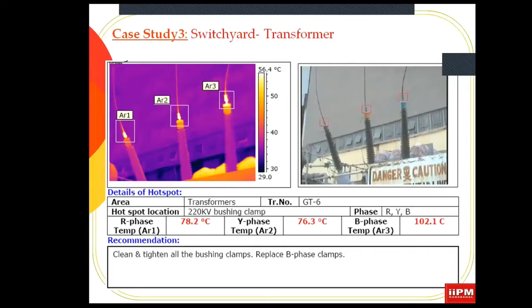So in the report, normally the transformer serial number, area, company's name, which component name, and according to the hotspot or line, it is recorded. From that we find the delta T. After finding the delta T or rise in temperature, our thermographer or consultant engineer or analyst gives the recommendation of what to do and what not to do.